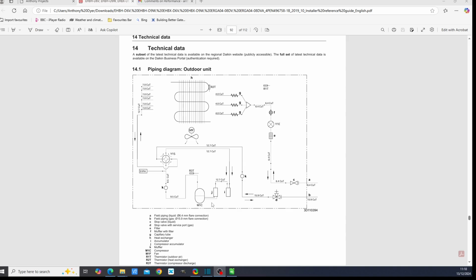So my installer is right. There is a minimum output for this compressor. But the thing is that I'm a control systems engineer. I also know he's wrong. There is an even lower minimum for every single motor, and that is off. You can still run refrigerant through here when this compressor is switched off.